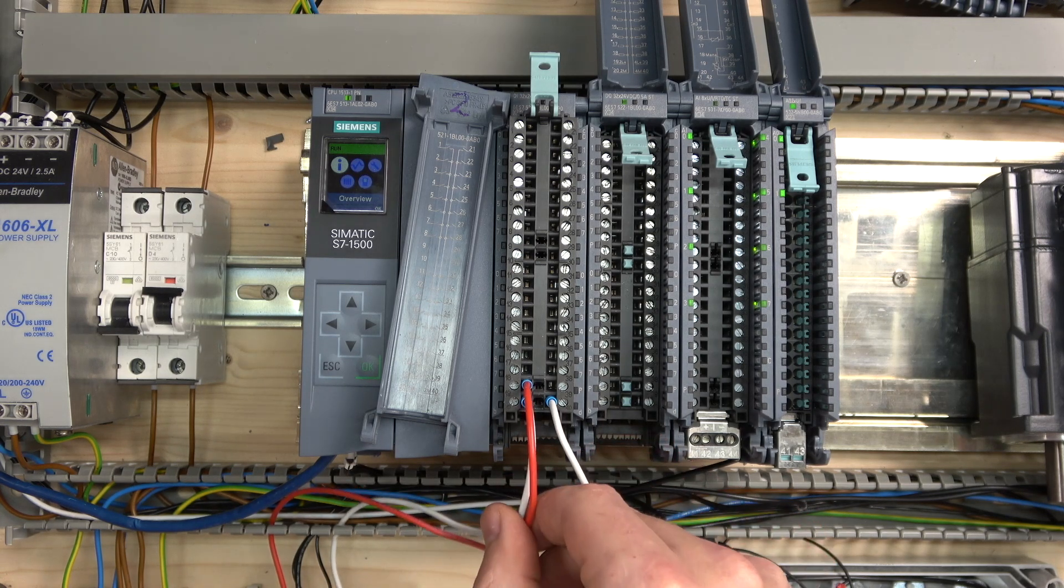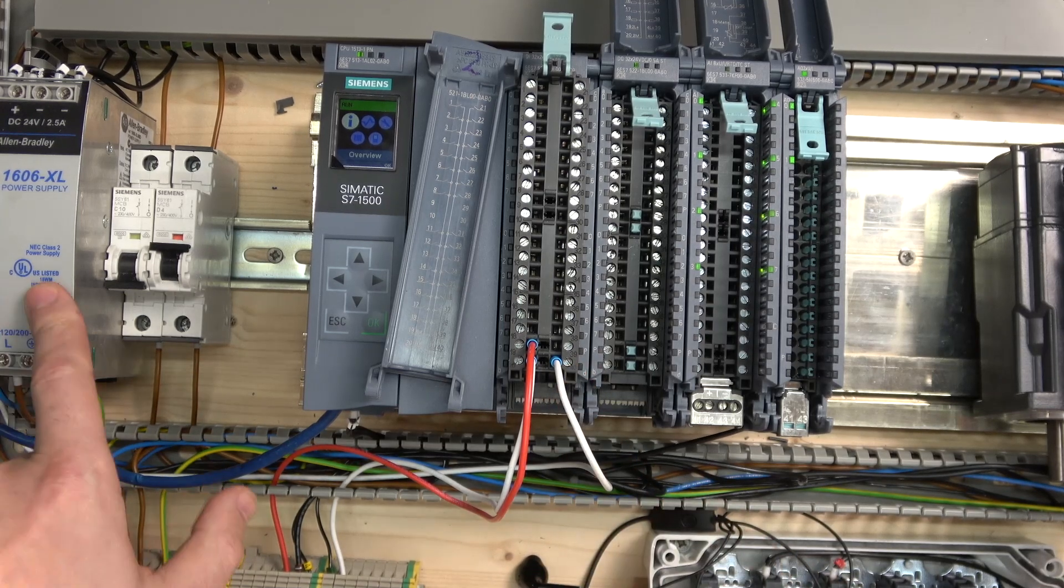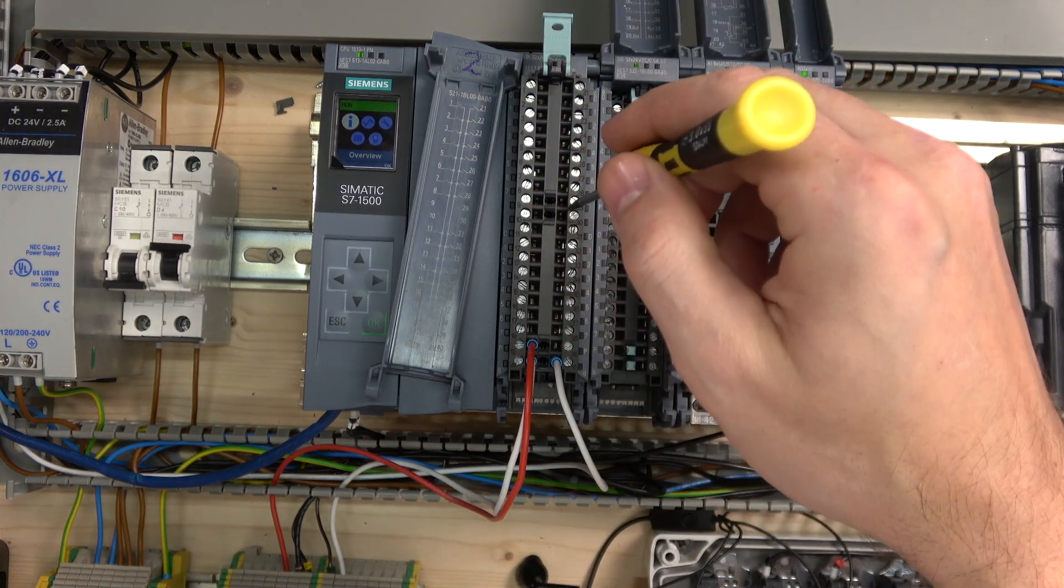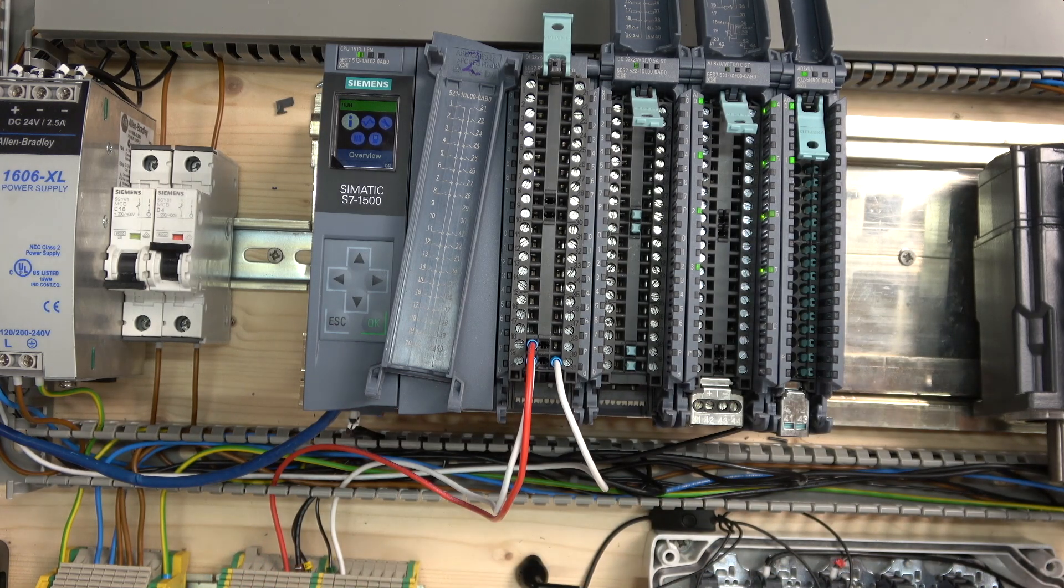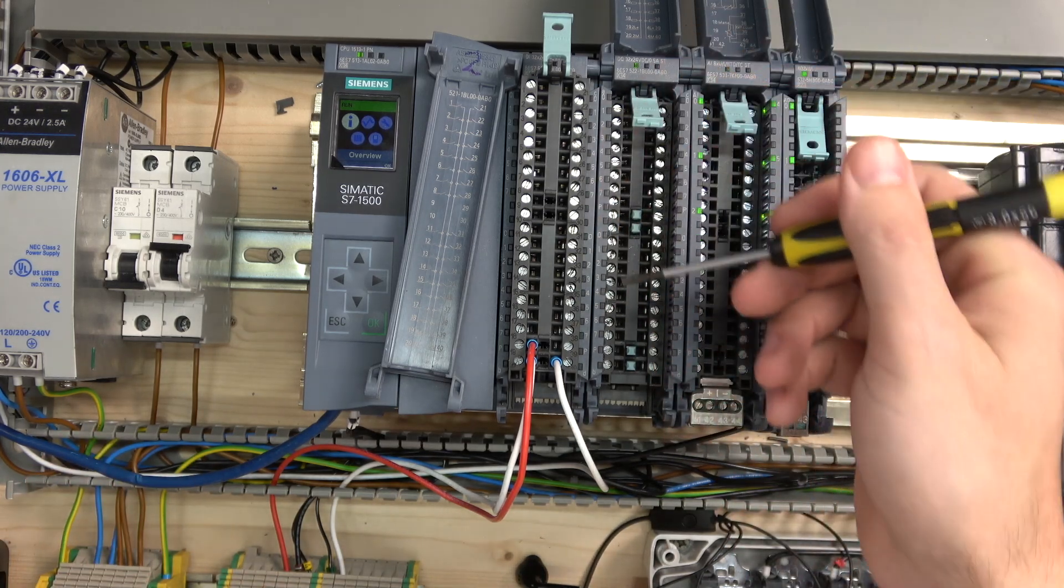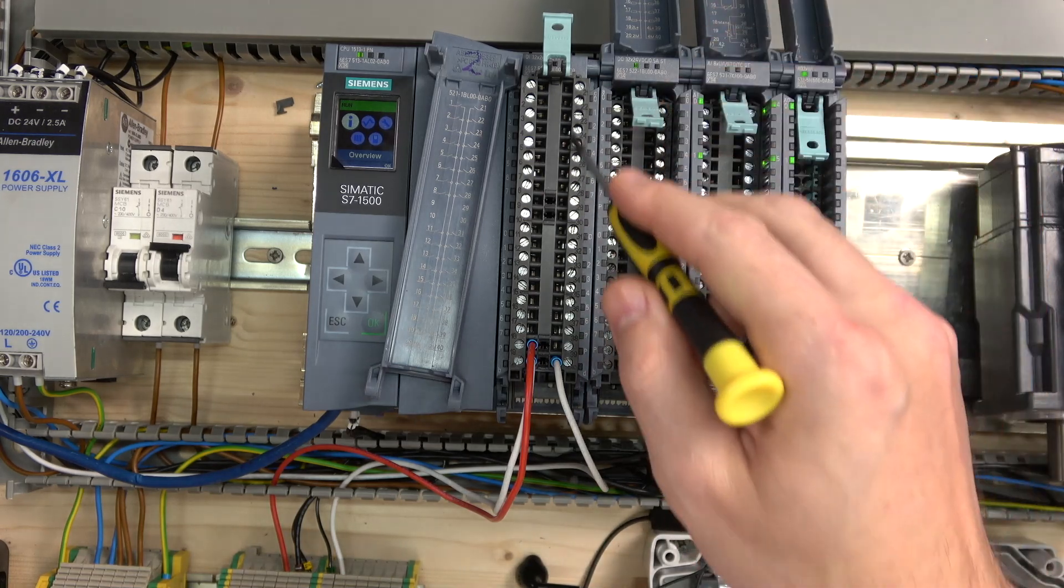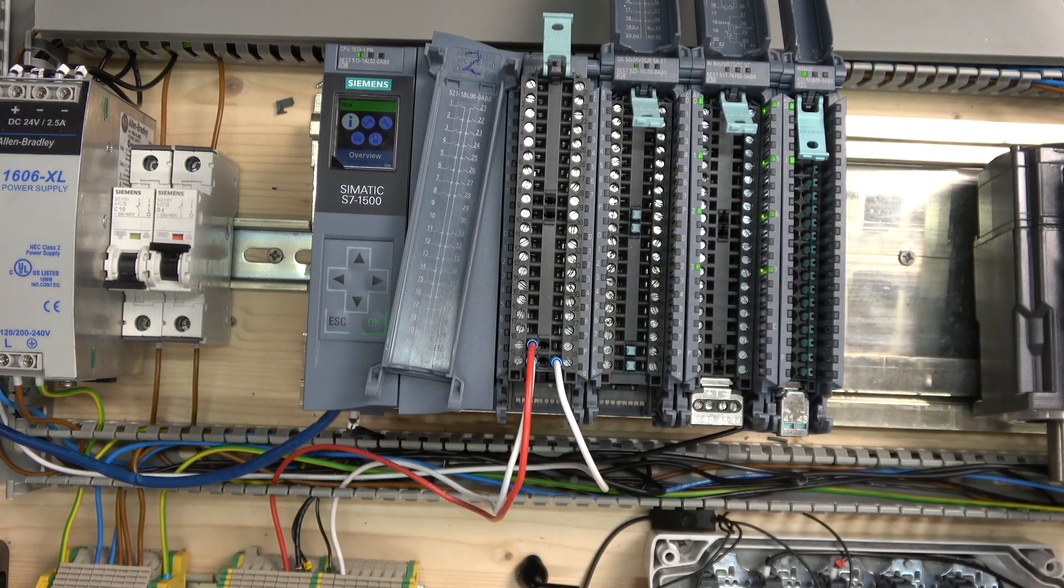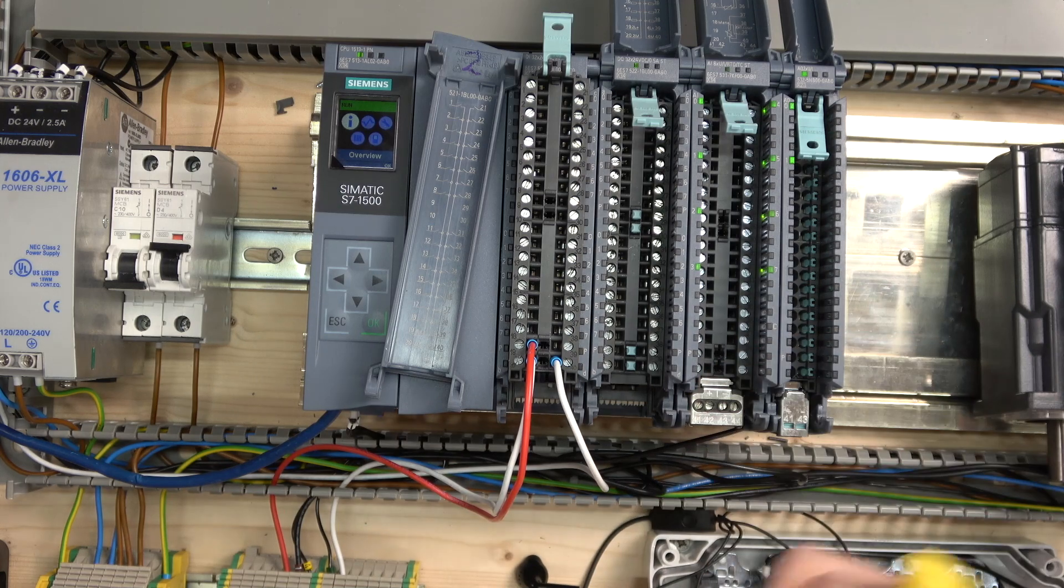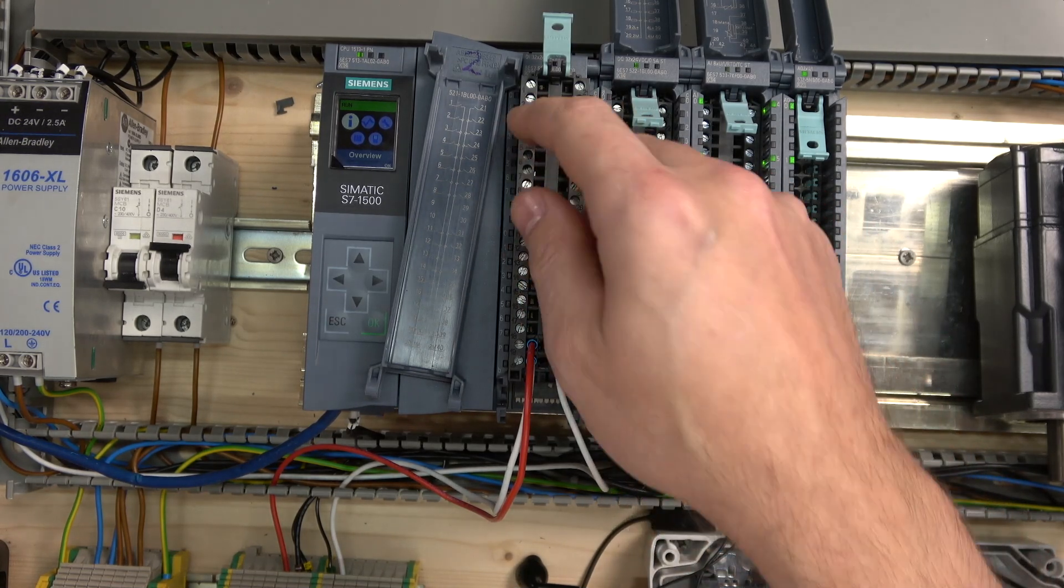This plus and this minus here is actually coming from the power supply. This minus in here is actually coming from this power supply and I'll show you what happens when you try to mix. The reason you would want two, one section for one, other section for the other one, is if your machine has got quite a large machine, it uses two power supplies and those two power supplies are sending the signals back to your PLC. You can use this card to utilize this card as much as you can with two different power supplies. So one power supply could send its signals back to this part of the section, let's call it the B part. Another power supply, the A power supply, could send all these signals back to the A part of section of this card. It's basically giving you an option to mix and match.